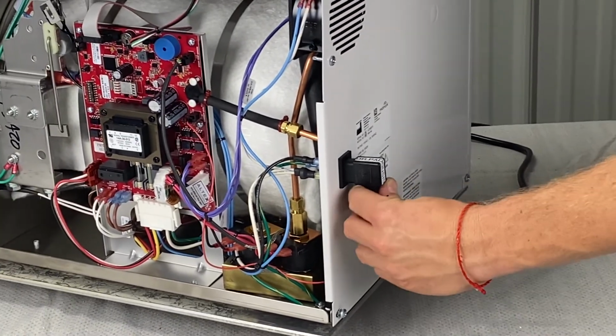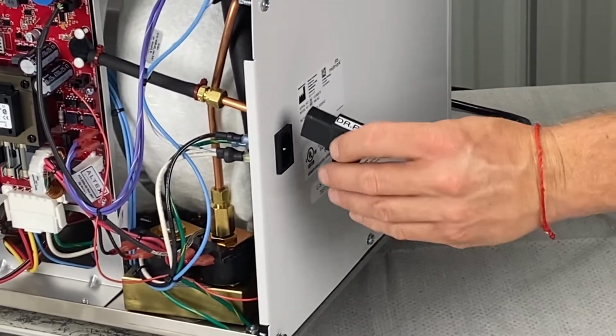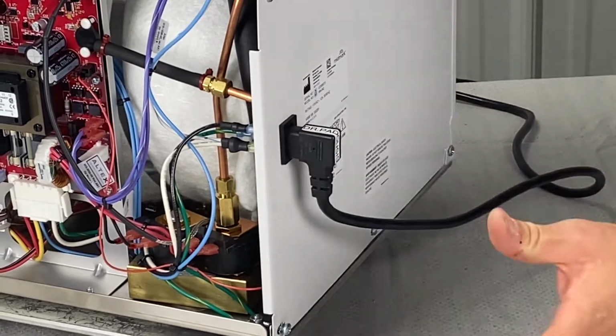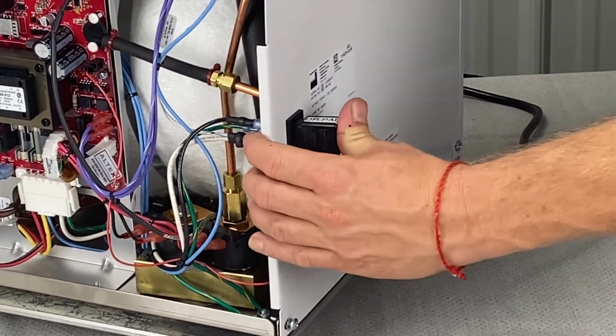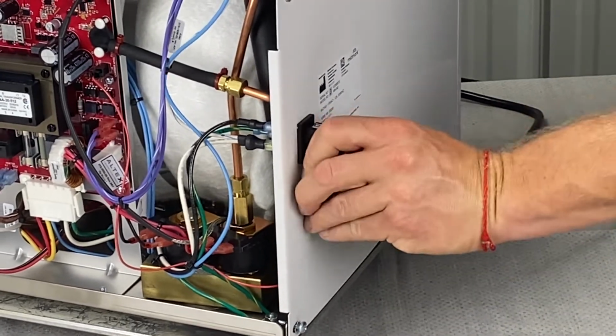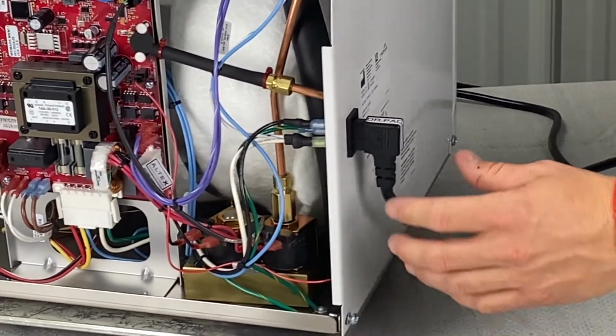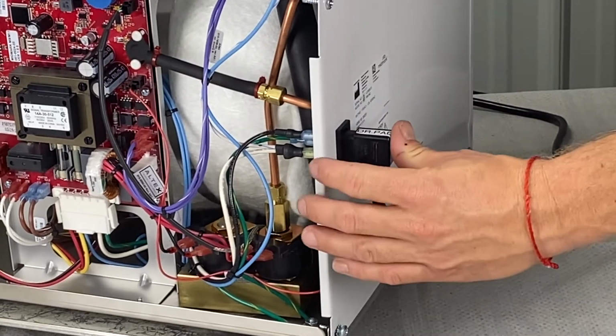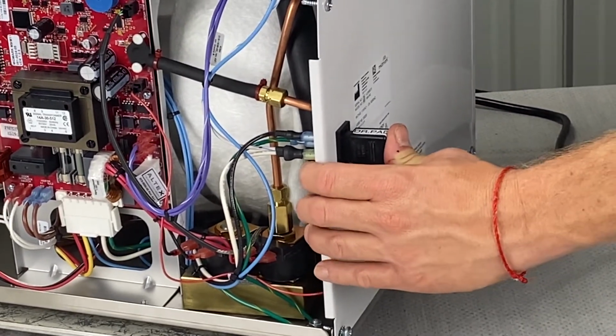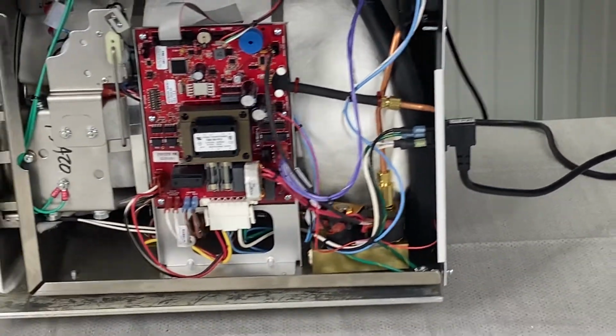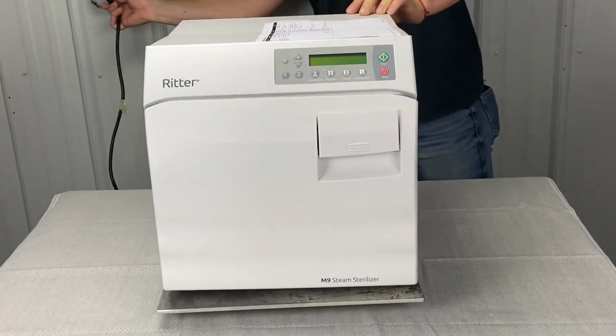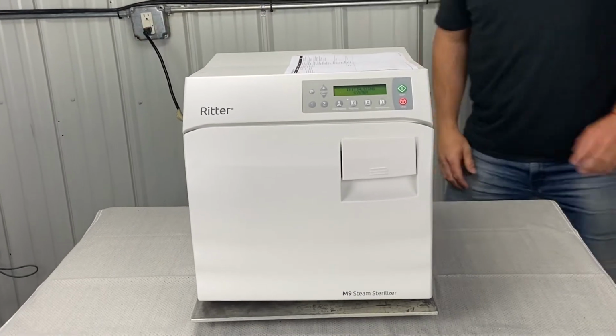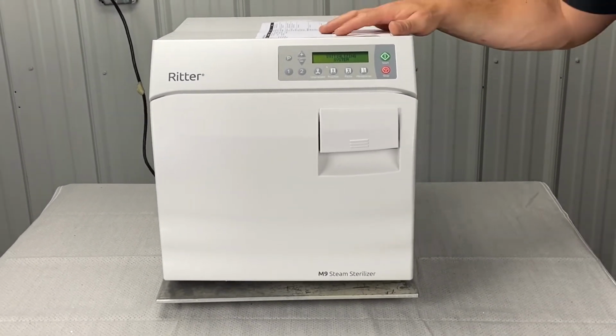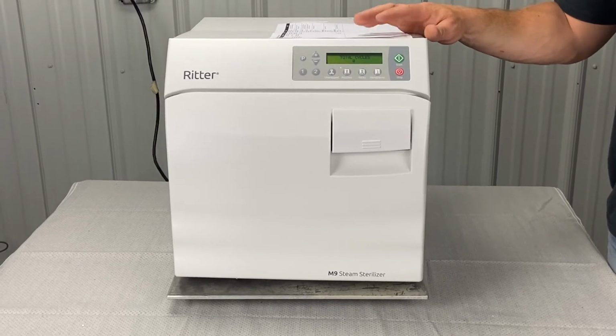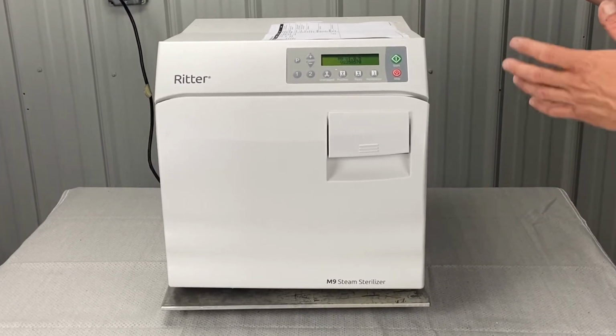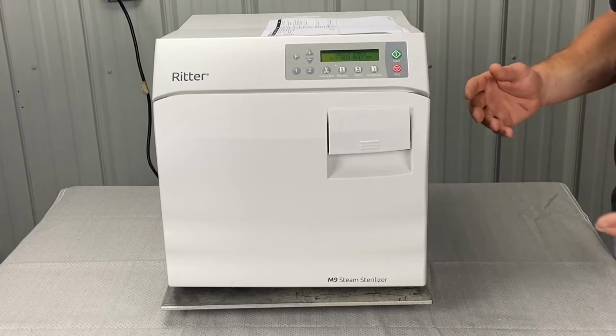Another common thing is that, especially with this particular part of the plug, see how I can leave it there like it barely touches? It needs to be pushed in all the way. If it's loose, you're going to get intermittent errors as people touch it, shut the door, whatever the case may be. So if you get this error, push that in, just double check. Often unplug and replug, that'll also solve the problem. Also, if you're ever in a situation where it directs you to unplug and replug, then you should unplug it for 60 seconds and then replug it in.